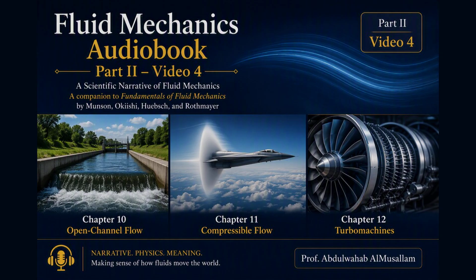Pump performance is described by curves showing head, efficiency, and power as functions of flow rate at a given speed and impeller size. The actual operating point is determined by the intersection of the pump curve with the system curve, representing elevation change and losses in the piping system.